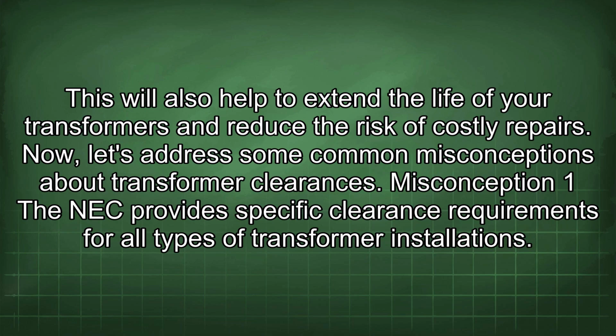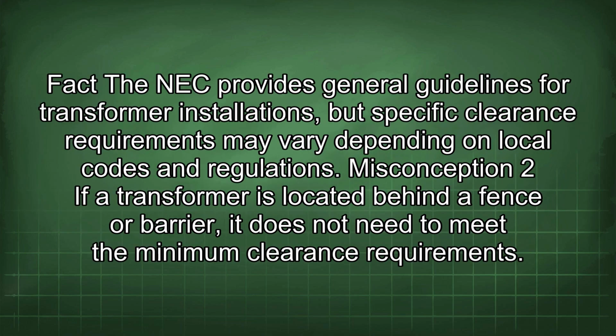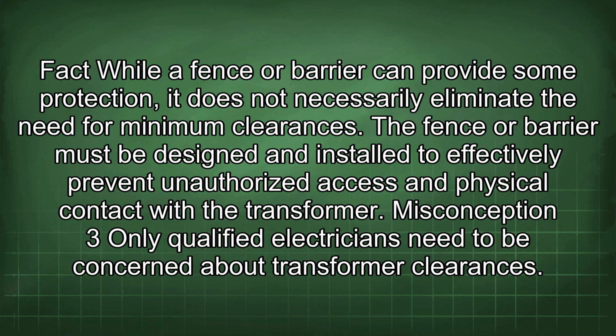Now, let's address some common misconceptions about transformer clearances. Misconception 1: the NEC provides specific clearance requirements for all types of transformer installations. Fact: the NEC provides general guidelines for transformer installations, but specific clearance requirements may vary depending on local codes and regulations. Misconception 2: if a transformer is located behind a fence or barrier, it does not need to meet the minimum clearance requirements.